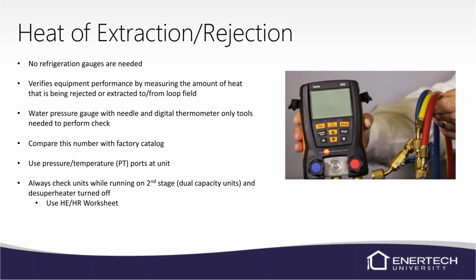Non-pressurized, because we can use a flow meter tool to check that. But on a pressurized system or a pump and dump open loop, those definitely need to have pressure temperature ports. Always check the unit when it's in second stage on dual capacity units.